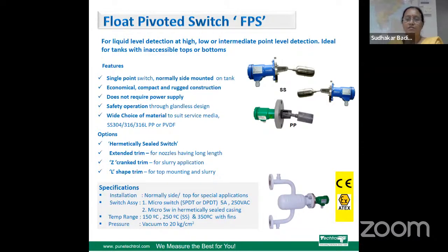Wide choice of material is available in stainless steel, PP, and PVDF. The switch is available with hermetically sealed switch. Extended trim is available for nozzles having longer lengths. Then Z crank trims option is available for slurry application. Then L-shaped trim is available for top mounting or slurry applications. So the switches are available with single micro switch with SPDT or DPDT contacts, or switch with hermetically sealed casing.